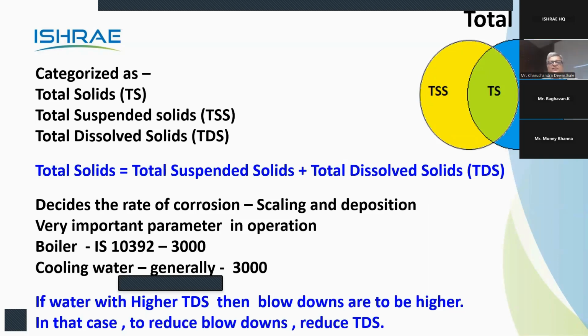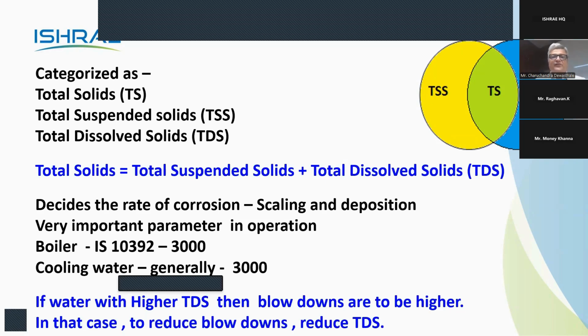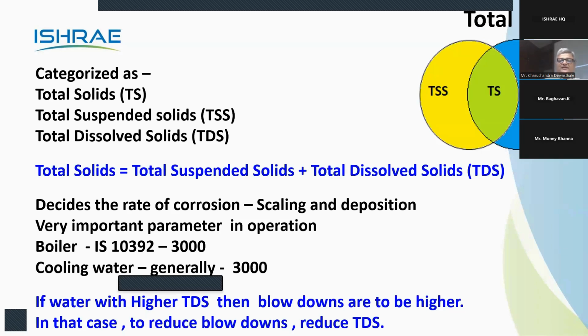Okay. So total solids are total suspended solids and total dissolved solids. Total suspended solids is TSS and total dissolved solids is TDS. This decides the rate of corrosion, scaling, and deposition. Very important parameter in the operation. Each of these parameters like TSS and TDS, we will look at very deeply in the next slides. But I'll give you how much it is. There is an IS standard, IS 10392, in case of boiler operations, where it says TDS should not go above 3000, or for cooling water, which is generally between 2500 and 3000.